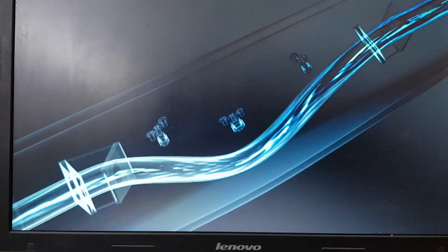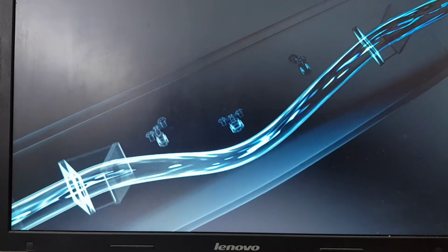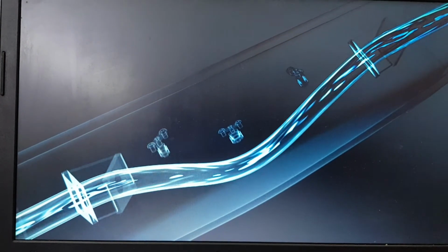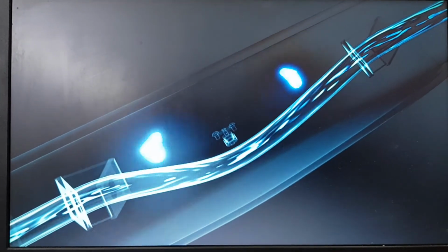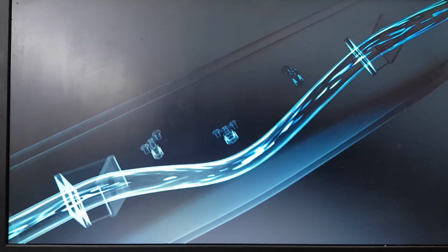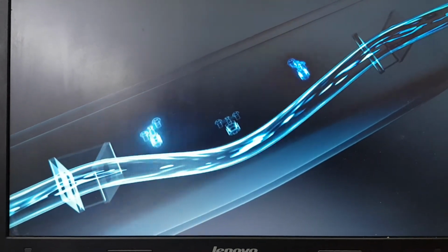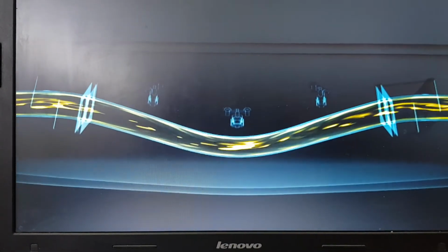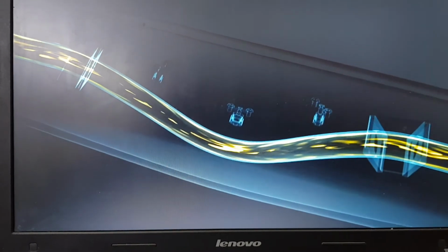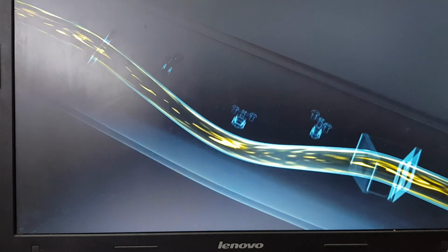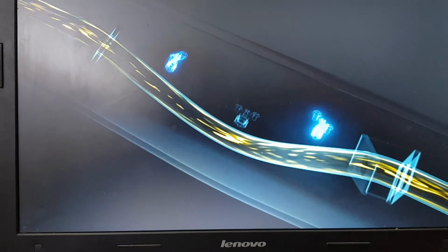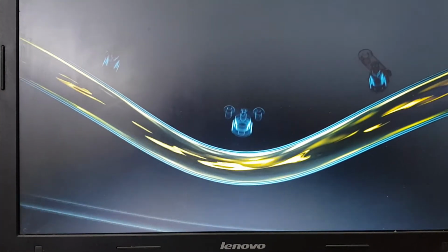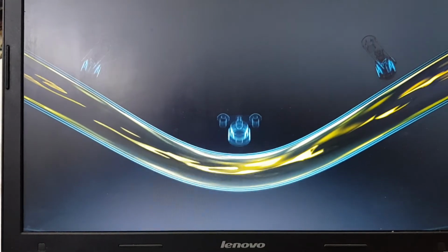The application of the Coriolis measuring principle doesn't stop here. It can also be used to simultaneously determine the density of the flowing fluid. To do so, the sensors also register the oscillating frequency, in other words, how often the measuring tube moves back and forth in 1 second. From the animation, it's clear that a tube filled with water oscillates more frequently than a tube filled with honey, for example, which has a far higher density. Thus, the oscillating frequency is a direct measure of the fluid's density. Both the density and the flow are determined simultaneously but independently via the tube oscillation.